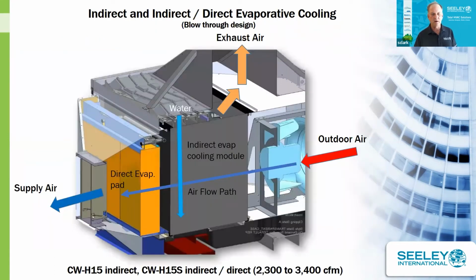So if we look at a cross section of our units that are made in Denver, we have a fan out here, an outdoor air fan, that pulls the air through filters, MERV filters. This fan is made by EBM. So it's a backward inclined fan that's directly coupled to an electrically commutated motor, an EC motor, high efficiency, and that pressurizes this plenum, whereby the hot air goes through the dry channels, clear out through the unit, and is cooled down. And then a portion of this air is directed back through the heat exchanger and exhausted out to the outside.